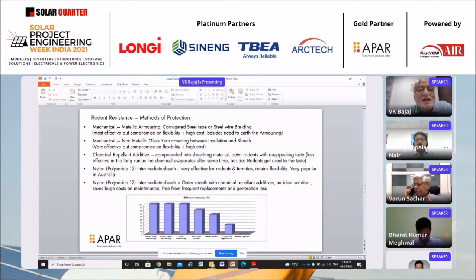Other methods are mechanical. You can do mechanical metallic armoring with corrugated steel tape or steel braiding, which is most effective, but compromises flexibility, has higher cost, and the steel armoring needs earthing. Another mechanical option is non-metallic glass yarn covering between the insulation and sheath. This is very effective, but compromises flexibility and has high cost.